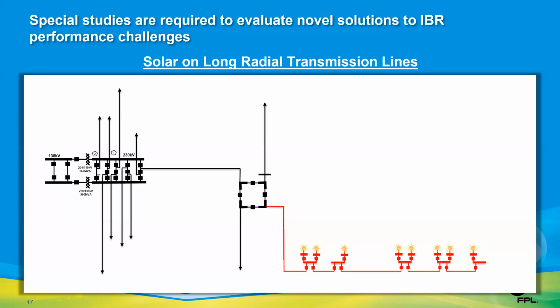So we developed both conventional mitigations and what I consider novel solutions to these reliability issues. I should mention first that the first thing we tried in EMT analysis was to modify the inverter settings. We adjusted the K factors, we adjusted the protection settings. We even adjusted the switching frequencies and tried a number of other things. None of that was effective. And in this case, the short circuit ratio was very low, so we're not surprised that those were not effective.